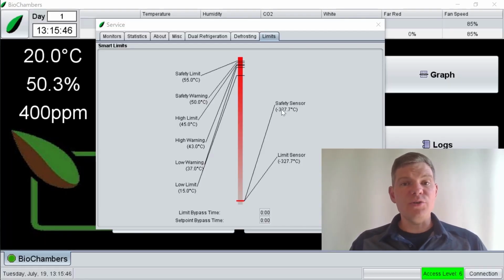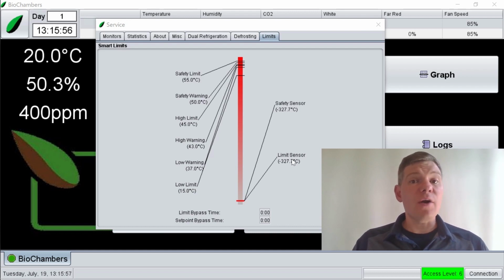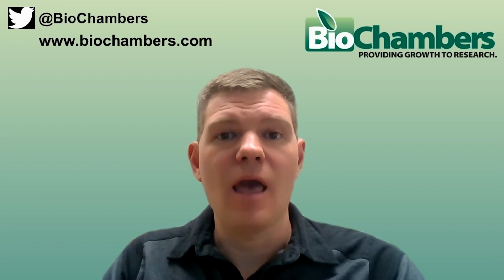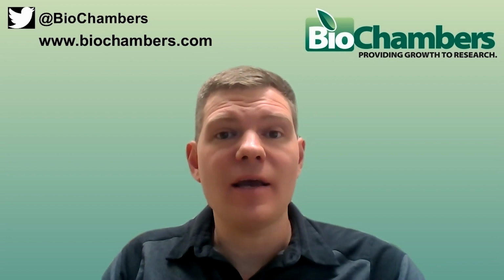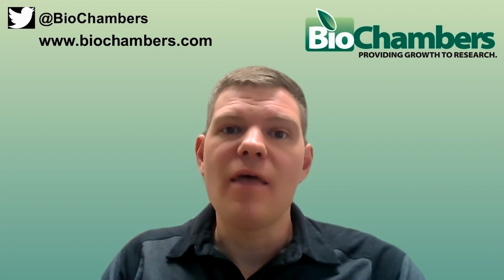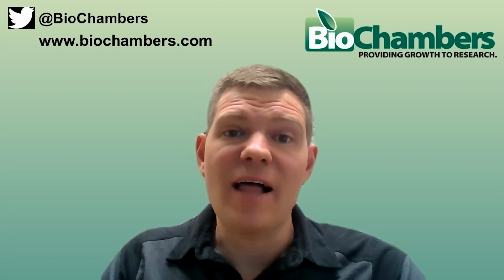If a temperature sensor is disconnected, VNet will show a check sensor alarm, and it will read a nonsense value of minus 327 degrees Celsius. Please contact us for how to access these temperature sensors in your equipment. If all 3 sensors are properly connected and receiving proper airflow, then a 1 degree difference of any given sensor is likely due to a drifted calibration.